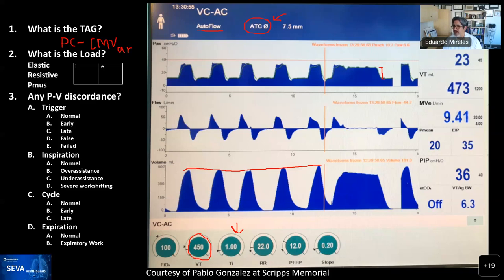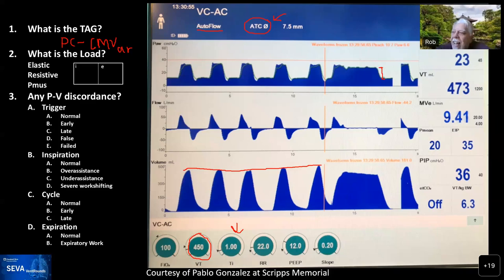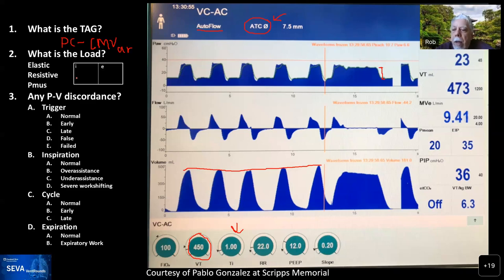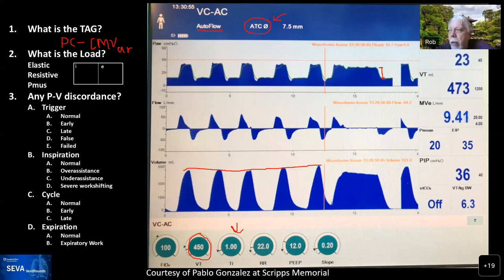Regarding PAV: PAV includes support for both resistive and elastic workload. There are two forms — the original and the Draeger version. The Draeger version lets you set how big a resistive load and how big an elastic load you want PAV to compensate for, whereas PAV Plus on Medtronic ventilators mixes it into a work figure. ATC can be thought of as simply the resistive workload support, so PAV does have that component.